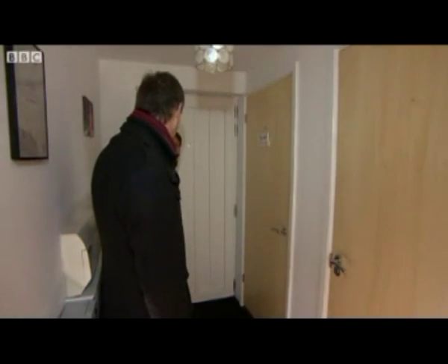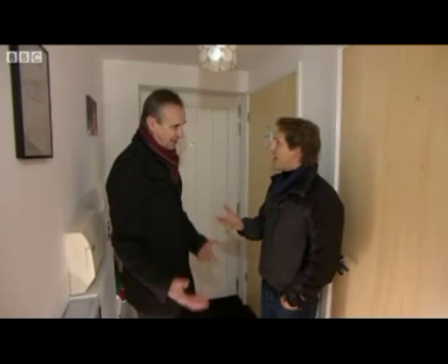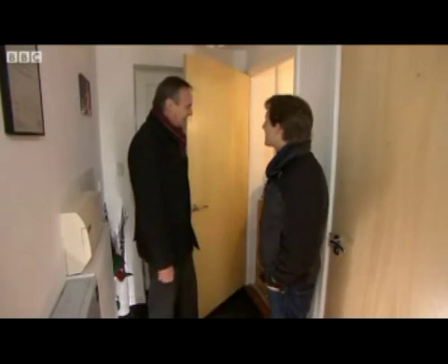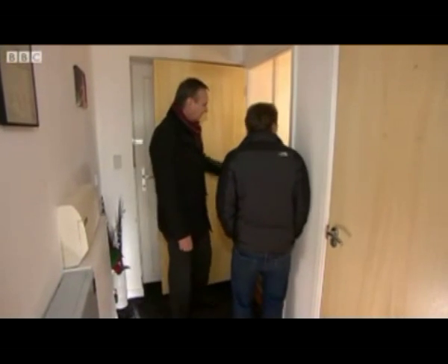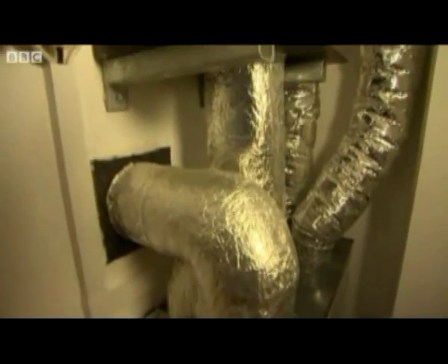It's a very comfortable environment. There are no radiators, no conventional heating system. So how does it heat then? There's a special piece of kit in here which does an awful lot of work for us. As stale air is extracted from the house, the warmth is transferred to the fresh air coming in. A small separate device, a bit like a boiler, adds heat if necessary.